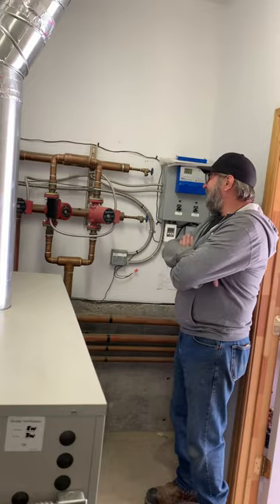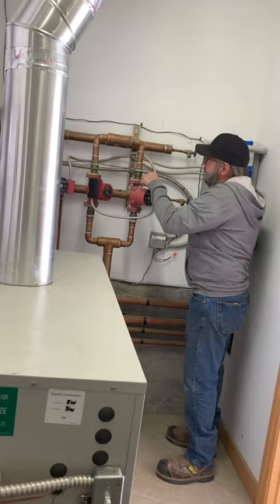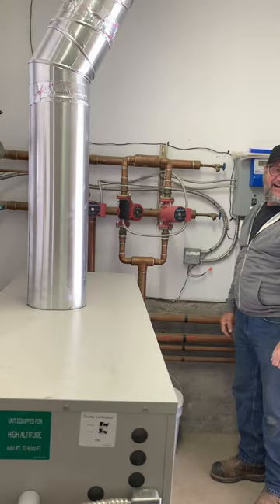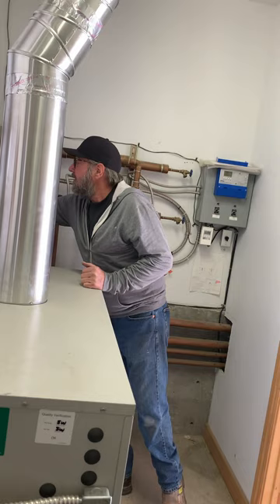No, or you can isolate it. They've got these little isolation valves right here, the screwdriver kind. This is the old style. Sometimes you get it, sometimes you don't. Sometimes you break your screwdriver, sometimes you turn it off. And then it's a forced issue with draining the system. The new ones look just like this. And even these, they go sideways.